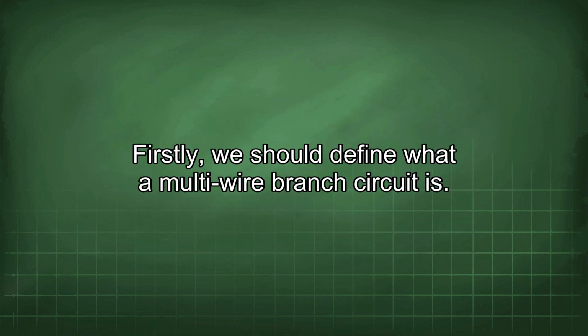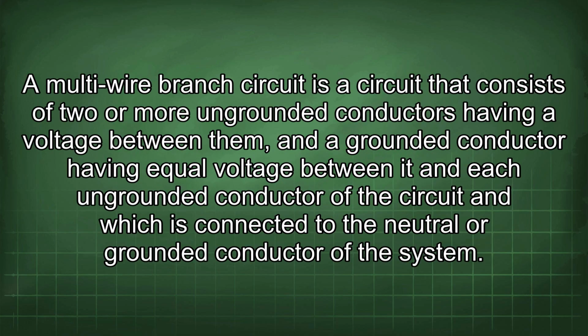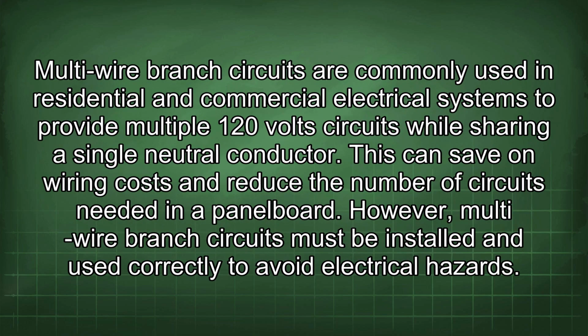Firstly, we should define what a multi-wire branch circuit is. A multi-wire branch circuit is a circuit that consists of two or more ungrounded conductors having a voltage between them, and a grounded conductor having equal voltage between it and each ungrounded conductor of the circuit, and which is connected to the neutral or grounded conductor of the system. Multi-wire branch circuits are commonly used in residential and commercial electrical systems to provide multiple 120-volt circuits while sharing a single neutral conductor. This can save on wiring costs and reduce the number of circuits needed in a panel board. However, multi-wire branch circuits must be installed and used correctly to avoid electrical hazards.